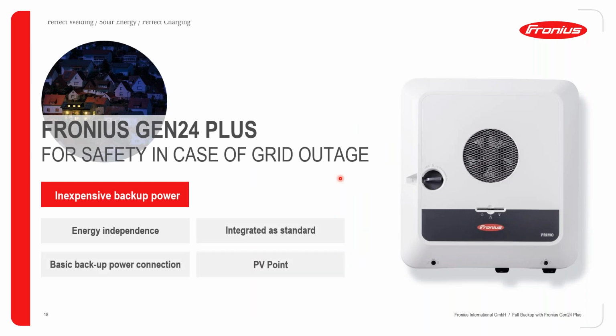So the Fronius Gen24 Plus provides you inexpensive backup power, and this is achieved without batteries. Okay, so if you're going to install the system without batteries, you'll only have the PV Point available whenever the grid goes down. So if the grid fails, the PV Point is activated and you will get single phase backup power of 3 kilowatts. Okay, and this is in the form of a PV Point.